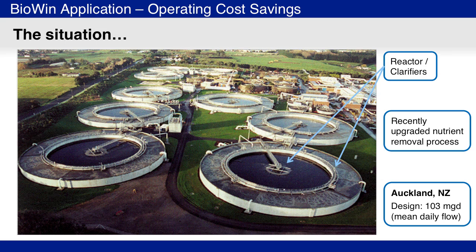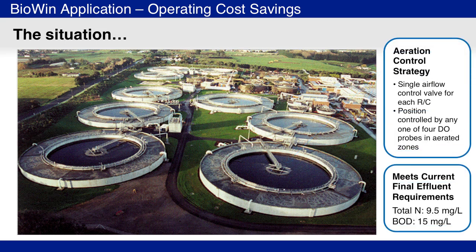This system consists of several reactor clarifier package plants. The influent was typical for New Zealand wastewater, and the design average daily flow rate was 103 million gallons per day. The plant was meeting its effluent requirements, which included BOD and total nitrogen limits. One aspect of the plant design was that the total air flow to each reactor clarifier was controlled by one valve.